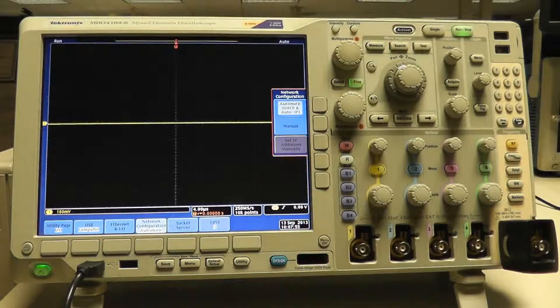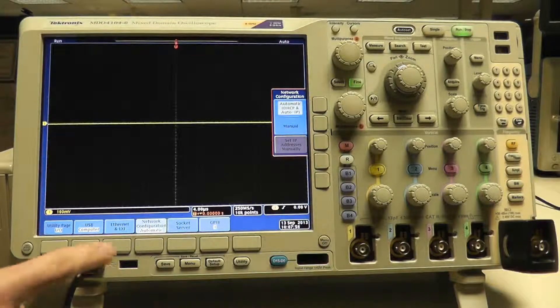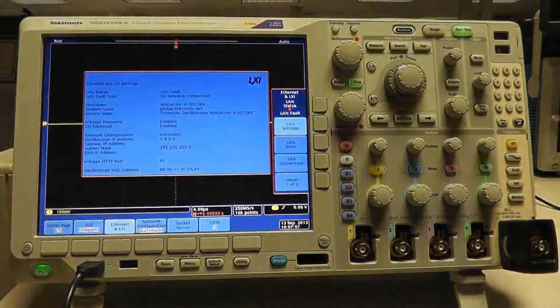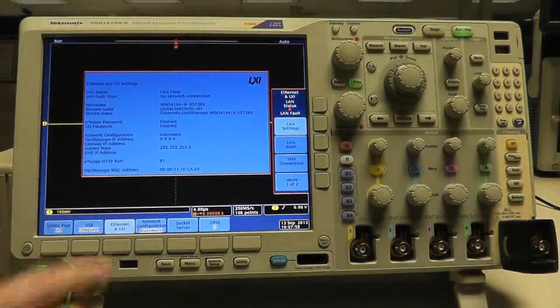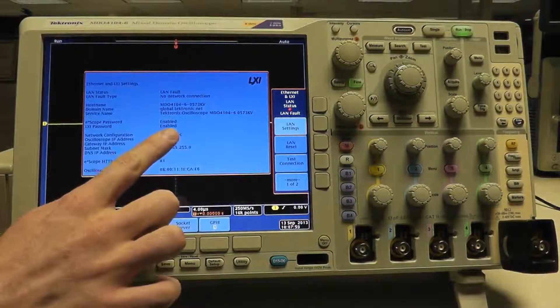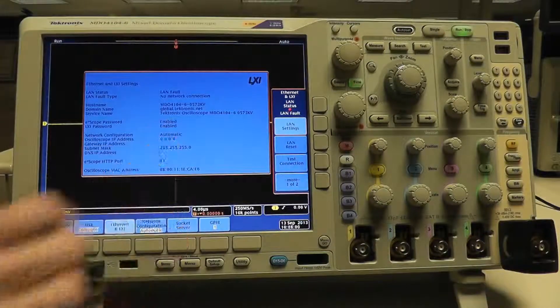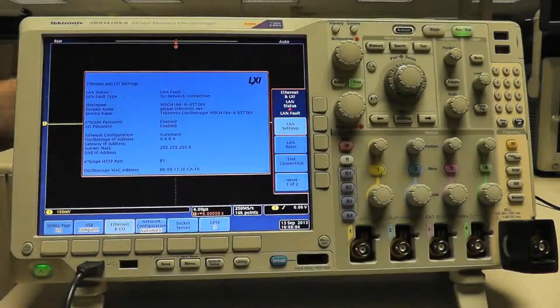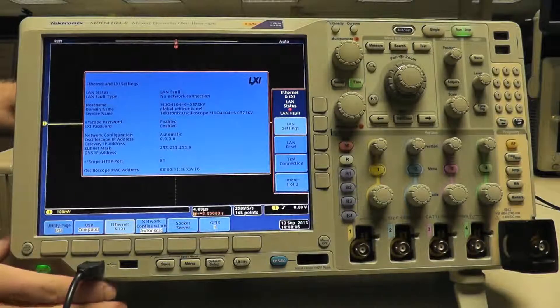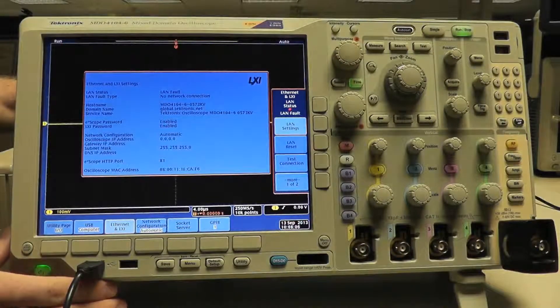Go back to Ethernet and LXI and LAN settings, and you'll see that the IP address has reverted back to 0.0.0.0.